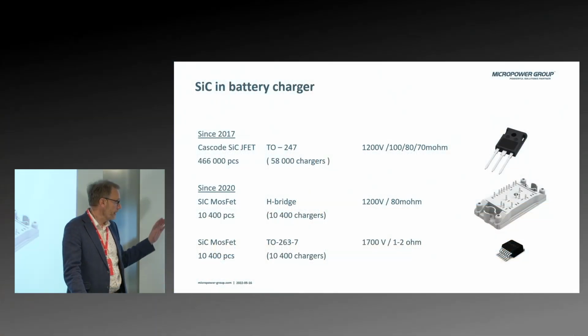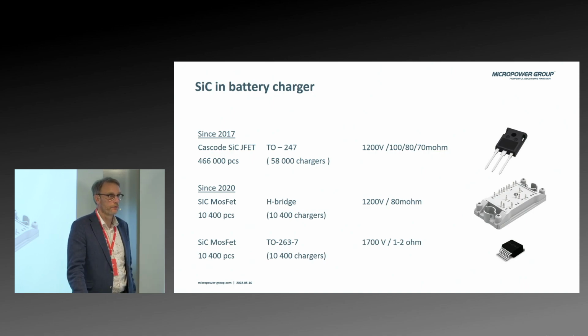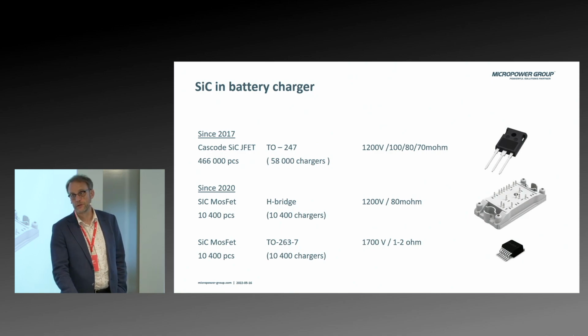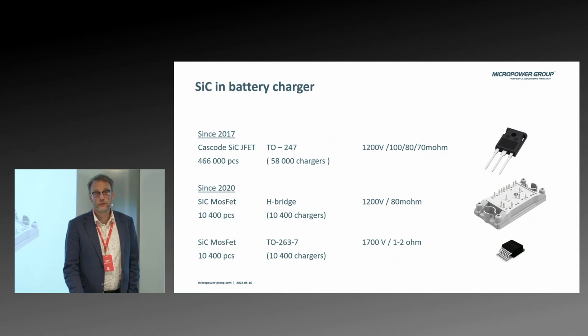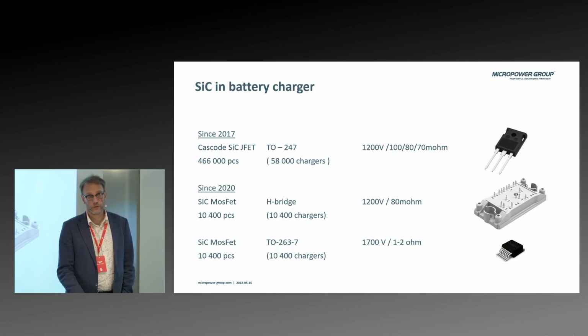At the same time, we also changed the auxiliary supply over to silicon carbide. This is something for industrial use that is very important. You need to have your 40-50 watts of 12 volt or 24 volt for your fans and your control system. And here we changed from a 1500 volt MOSFET over to a silicon carbide one.